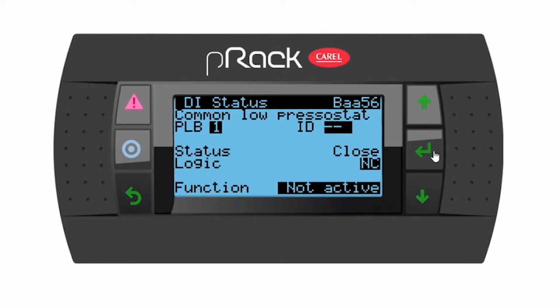Common low pressure stat. Do you have a system LP switch? If you have one, you're going to assign it. And also, is it normally open or normally closed? So as per my notes, we don't have one, so we're just going to go down. Common high pressure stat. So do you have a global HP? If you do, you're going to assign it, and the logic for it is going to be either normally open or normally closed. So if you have it, assign it. I don't, so let's go down.